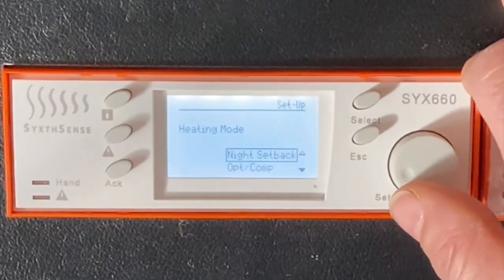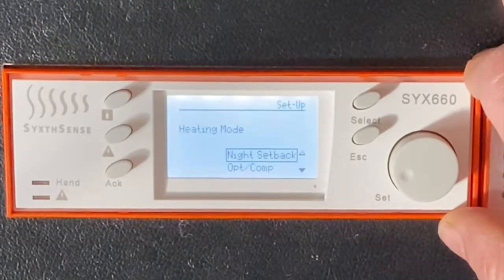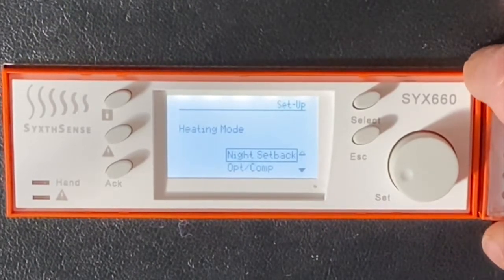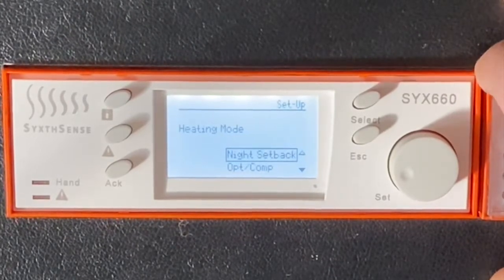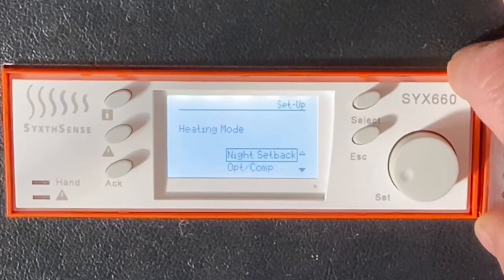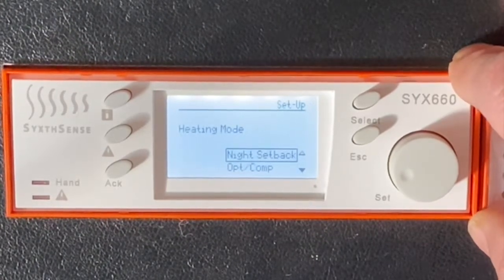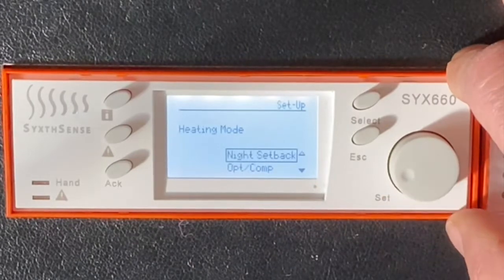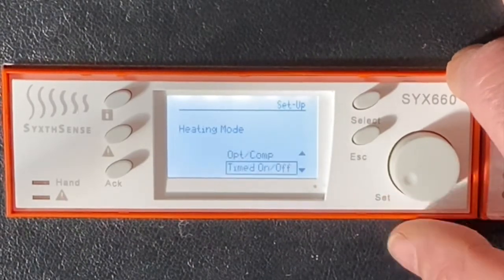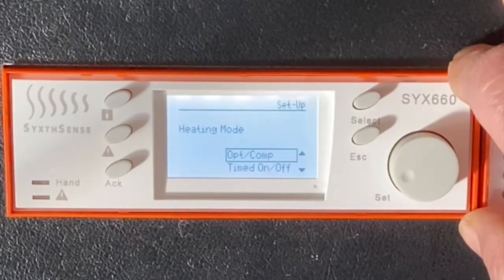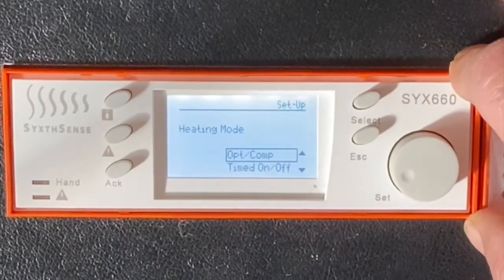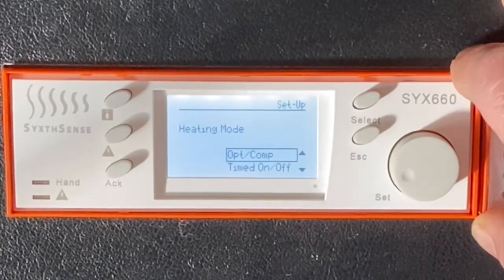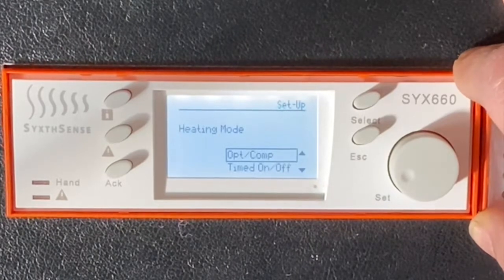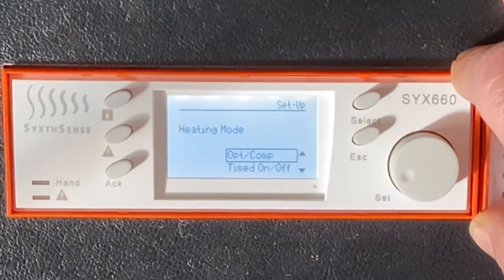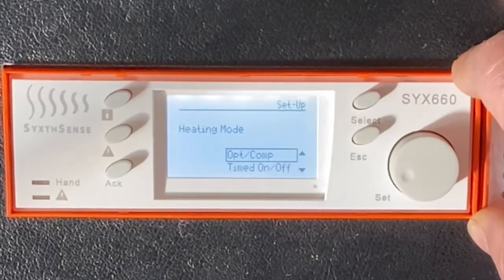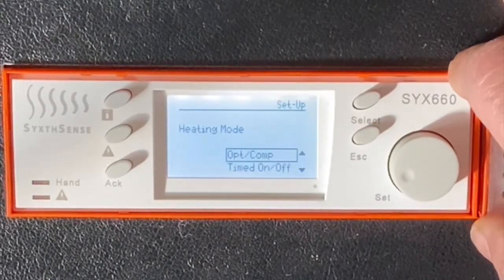If we press select onto that feature, we can choose night setback, which is something we would use for a permanently occupied building, something like a retirement home, where we only want to reduce the heating at night time. We don't want to turn the heating off. So that would be like a day-night setback function. Optimizer compensator is the one we're going to use. It has a self-learning adaptive heating time function, and it will maintain that day temperature throughout the day, and it will optimum off should we have that feature enabled before the end of the day if we've got surplus heat capacity.